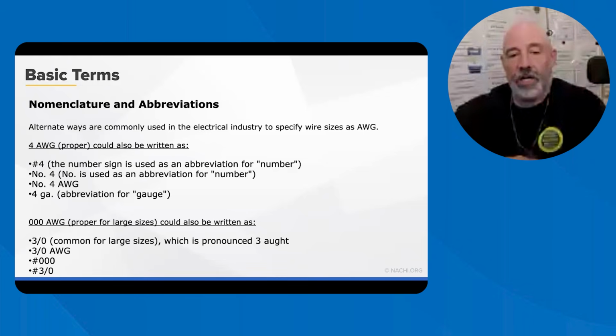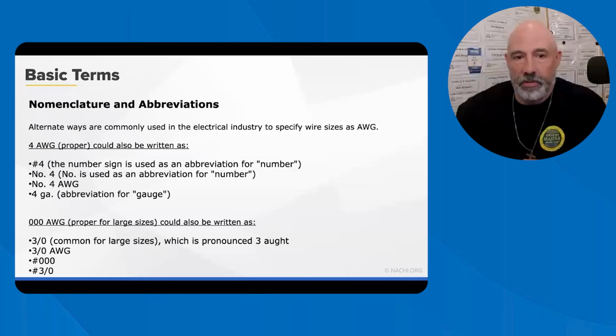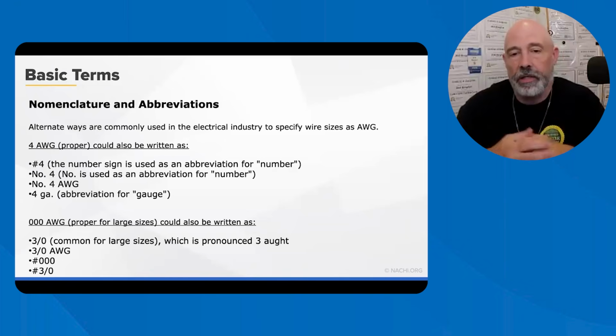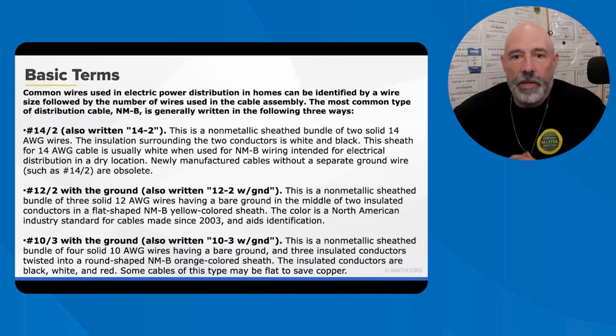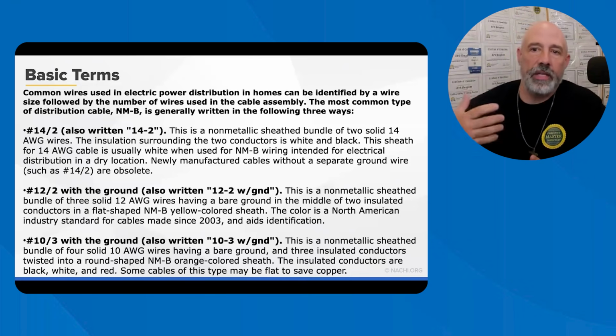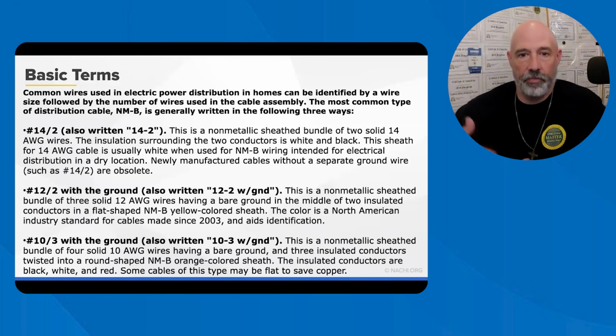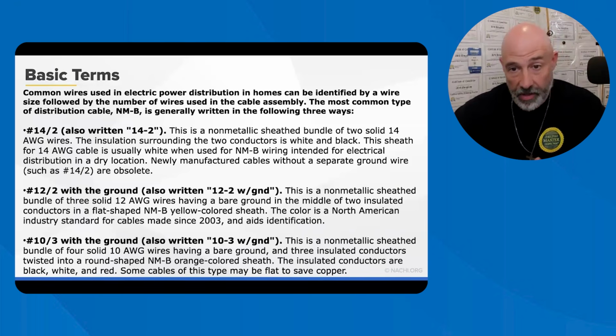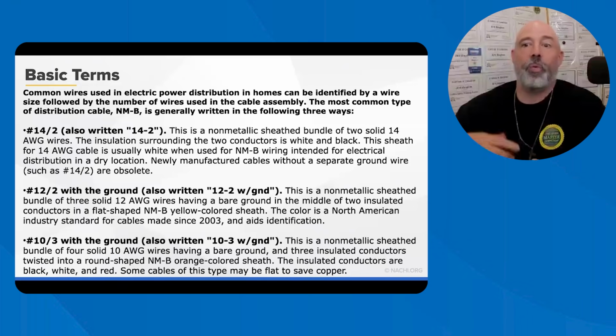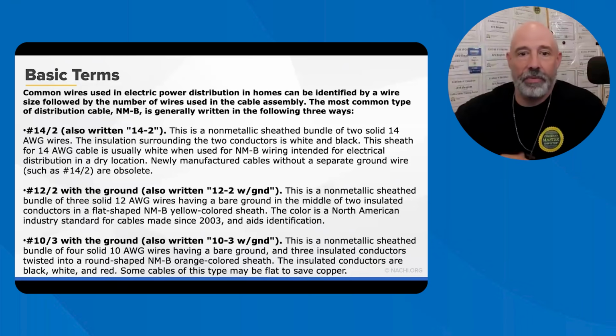And a lot of times when I get the callbacks, that's when we actually start talking a little bit more in depth. But for the most part, it's really awesome to know a little bit so that you know how electricians talk to each other. So, common residential cable types. Residential wiring is typically identified by the conductor size followed by the number of insulated conductors in the cable. You got the 14-2 with ground, which contains the black hot and one white neutral, and then the bare is the ground. You got a 12-2 with ground, which contains a black hot, one white neutral, and one bare grounding conductor. Then you got the 10-3, which contains a black and a red wire, a white wire for the neutral, and one bare ground, commonly used for 220 volt appliances such as your dryers and your ranges.